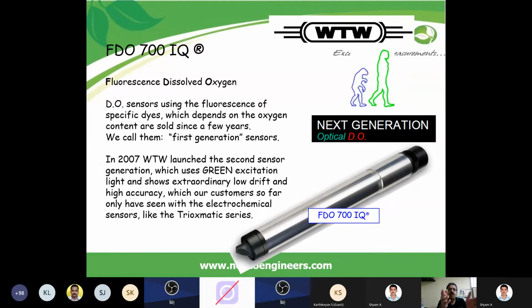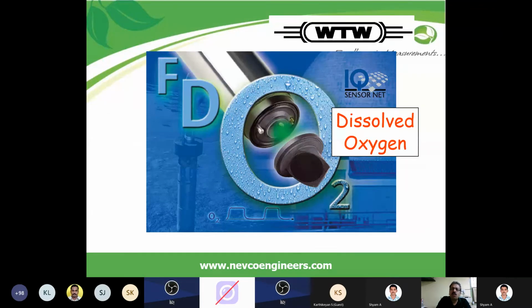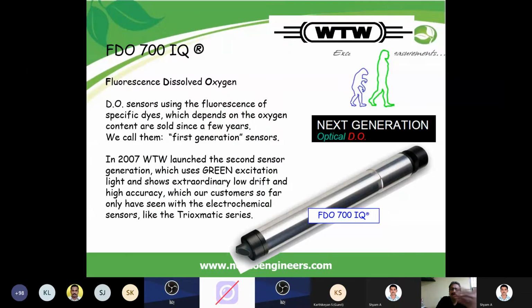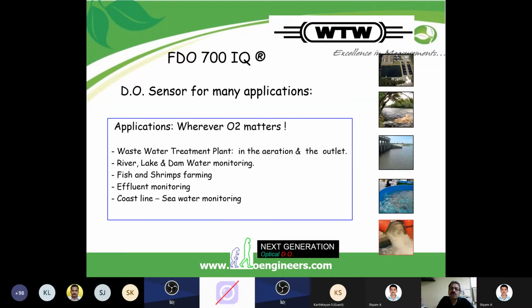But if you measure with a sensor exactly how much oxygen is in the water, once it achieves 2 milligrams per liter, for example, then the motors can be stopped. With a measurement, with a relay, or with a VFD, variable frequency drive, we can very well control the motor with this sensor. So this dissolved oxygen sensor will be very, very helpful in most process applications, and to save power, because here the motors of the STP plants are running 24 into 7.